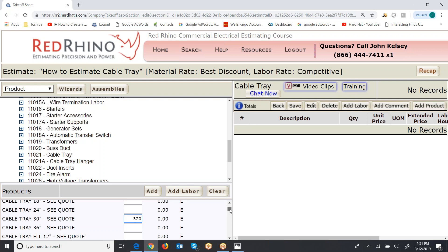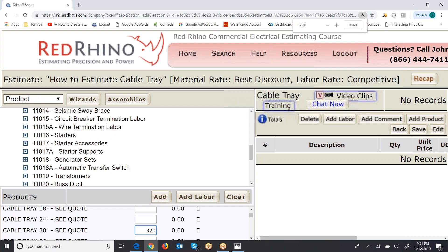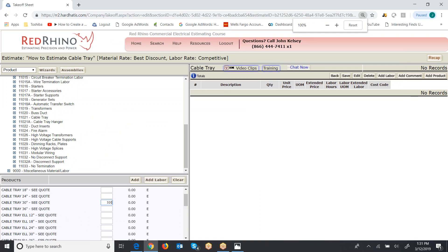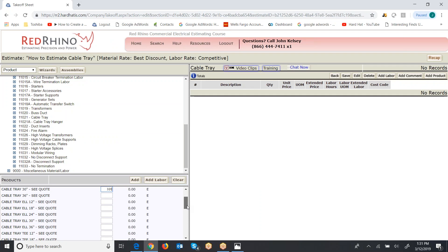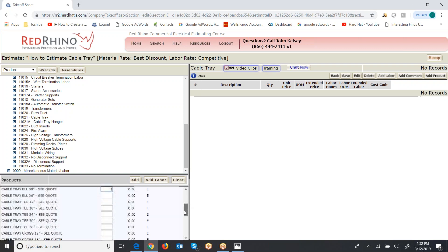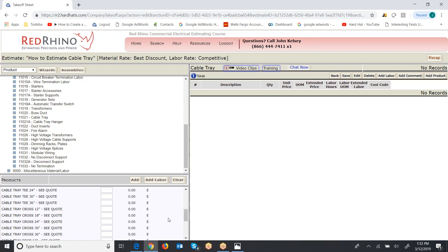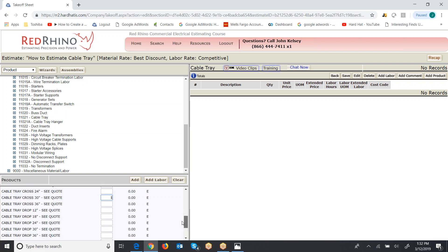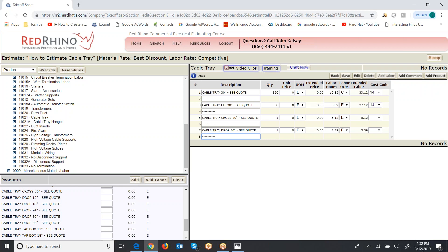So 320 feet of cable tray, 30 inch. Let's say that there's eight 30 inch L's or elbows or 90s. No T's, but there's one cross 30 inch. And let's say that there's a 30 inch cable drop, just one. So again, I just put the quantities in here like a laundry list. I click add and it populates the labor over on the right. Now I'm going to save it right here.